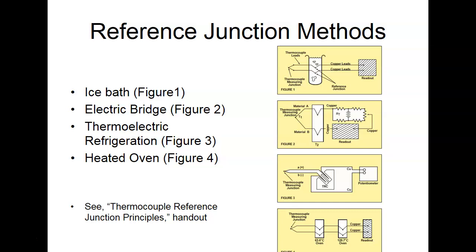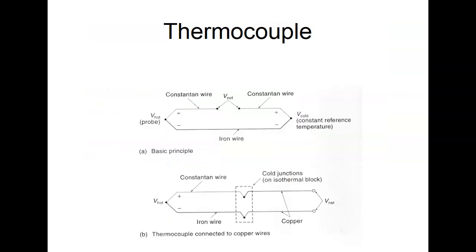So that means if it breaks, guys, we don't want them to twist them together. Basically, you just need to buy a new thermocouple. So this is what we're talking about. Thermocouples, we have to have what we call a cold junction. This is your reference junction. Then we have what we call a hot junction. So again, we got to run these in pairs, and one of them is your reference. What does this voltage mean, right? What does this voltage mean?